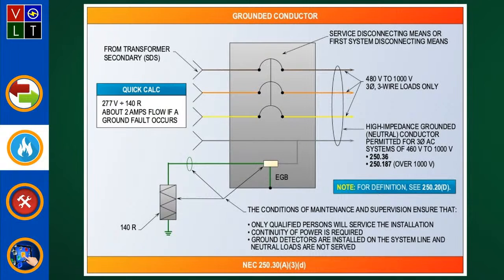Right, over time. I know this because there was a code change a couple of cycles back where you have to identify the neutral at the service. Yeah, and that's all in 200.6(A), (B), and (D), where you're going to pick all that up. So if you have both systems, you have to pick a gray for one and a white for the other, right? You can't just pick white for everything. Sure you can't, because of what happens. I'll just make up a problem to give you an example. Let's say I have a 480/277-volt system that comes to the mill, and I'm just going to make something inside the building, not two different power sources coming to the building.